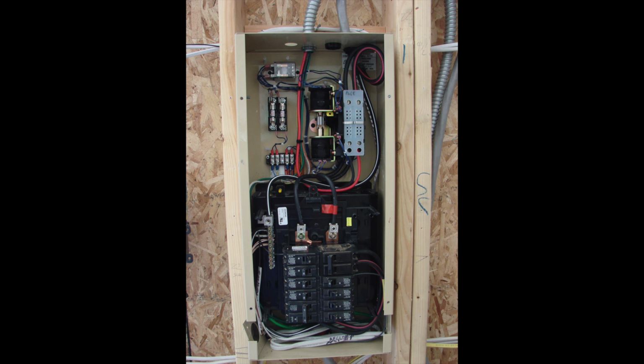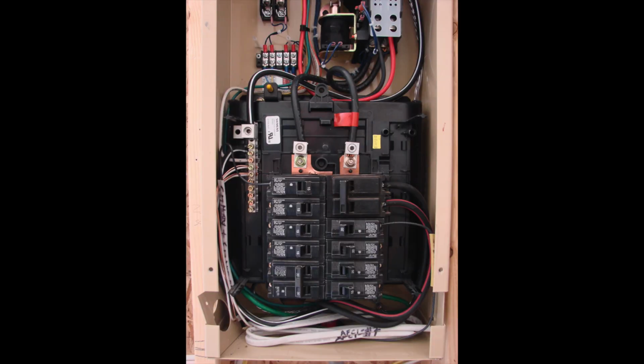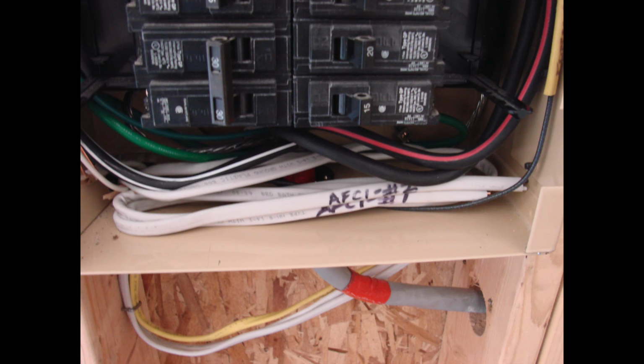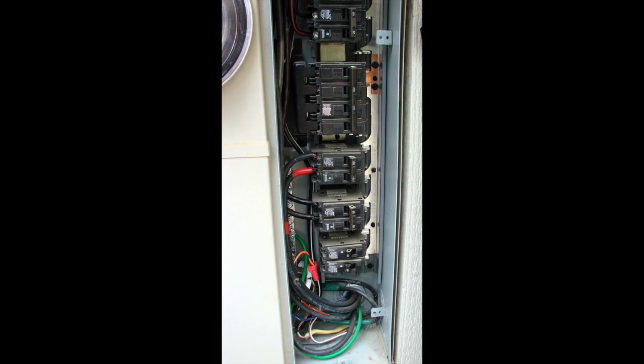So we have our transfer switch mounted. It's wired up from this side of the generator, and then we work our way back towards the panel. And of course, making the connections in the electrical panel is the last thing we do. We want to make sure everything is covered up inside of the transfer switch panel.